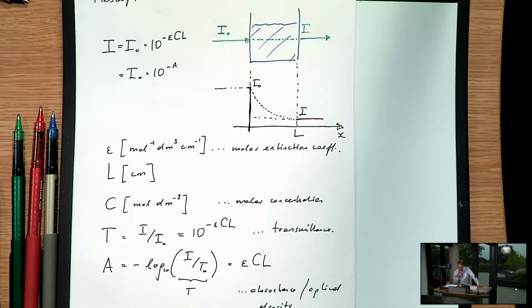And what that means is that in practice, absorption on its own is a measurement that is only possible for two orders of magnitude at most of measuring concentrations. So you need to have A between 5% and maybe 100% for you to say anything.